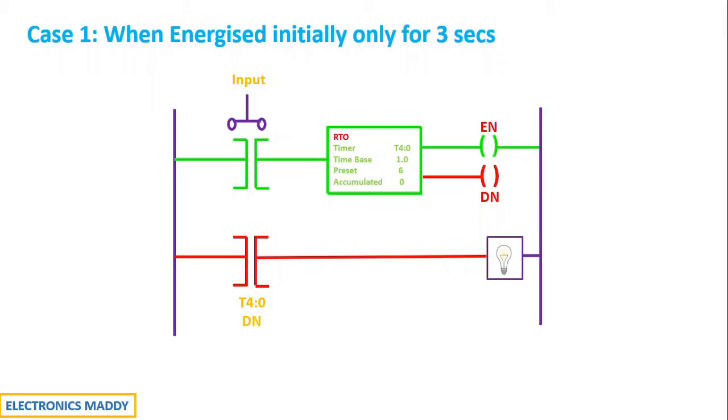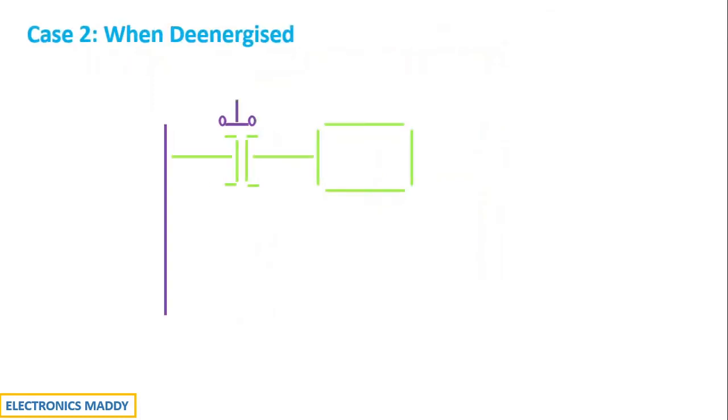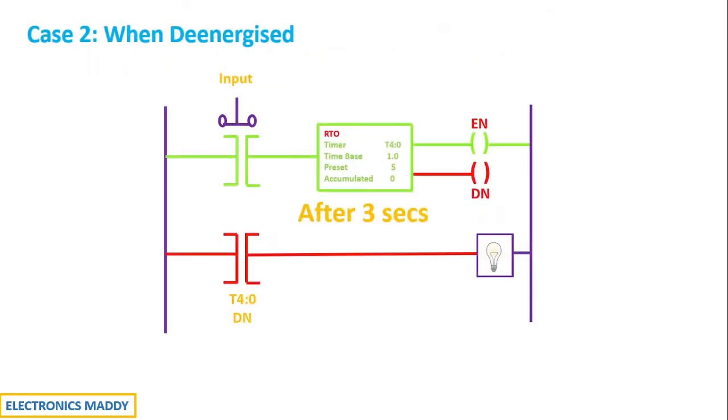Considering that as case 2, I will be starting off from the point where we left. After 3 seconds, I will be de-energizing this by releasing the push button. Once I release the push button switch, the contacts get de-energized, the rung gets de-energized, the timer gets de-energized, and the Enable goes low instantly. It is often understood that Enable always follows the input. And that is why it goes high to low and low to high depending upon the input conditions.